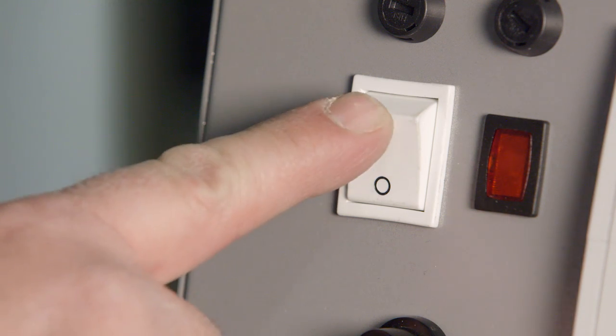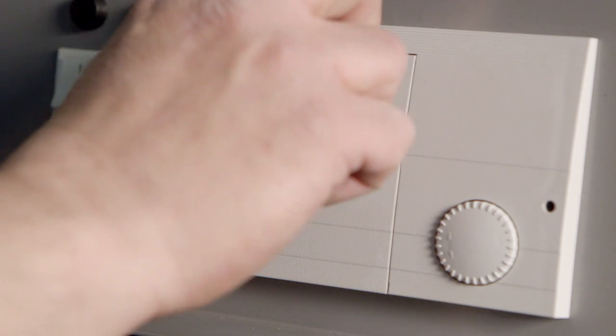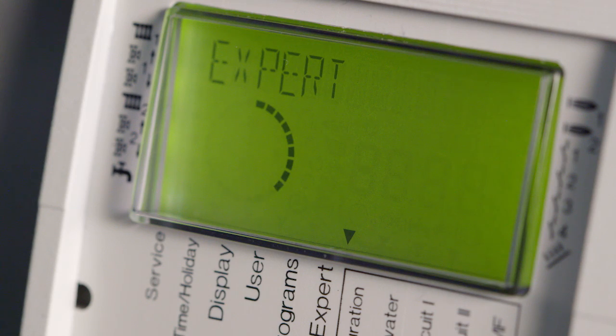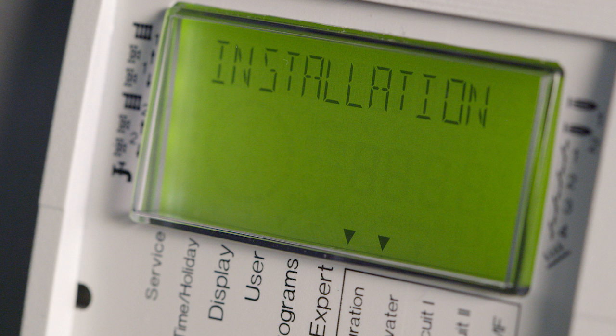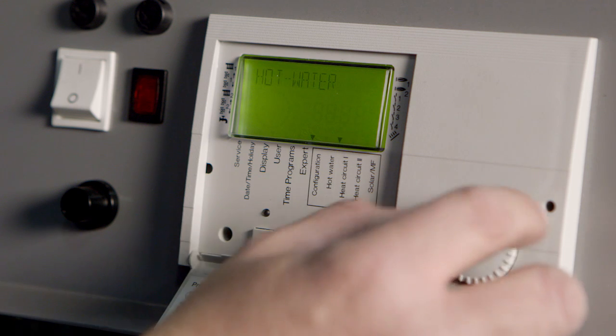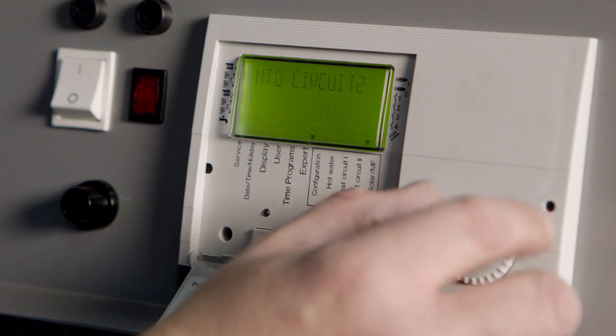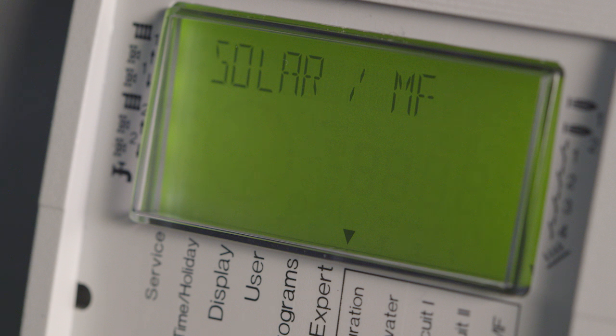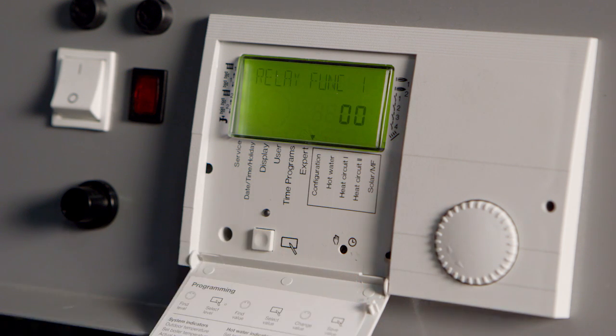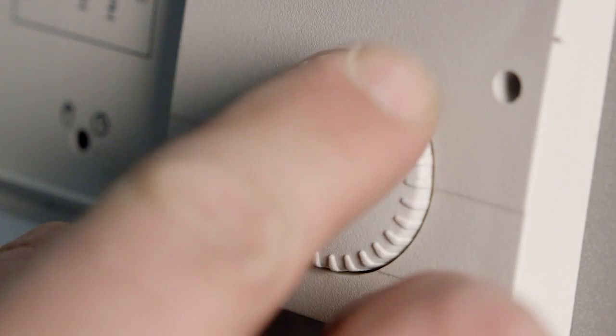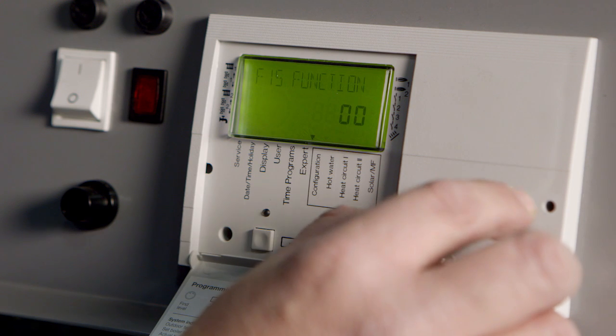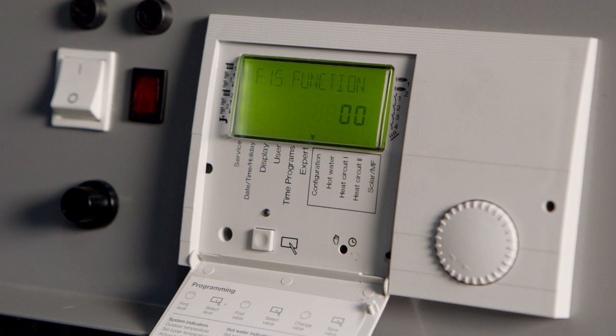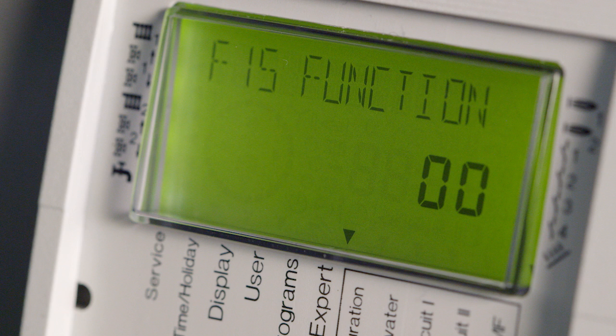Start by setting the on-off switch to on and then open the front panel. Turn the rotary knob clockwise to Expert Menu. The first submenu you'll see is Installation. Continue scrolling through until you find this. Now that you're in Solar/MF, press the program key to enter the Solar/MF submenu as shown. Turn the rotary knob to scroll through until you find F15 function. Its currently stored value is 00.